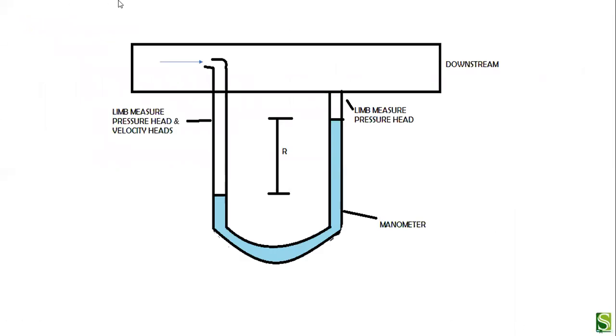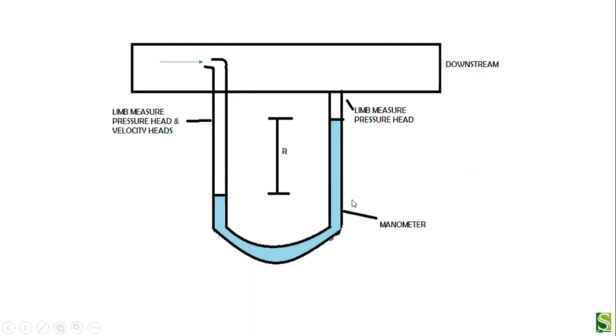This is the diagram of a pitot tube. One tube is in line with the upstream and the other is perpendicular to it. When the fluid flows from the upstream, the velocity increases in the tube and due to that the pressure decreases. The difference in pressure height can be read from the simple manometer connected to the pitot tube. The pitot tube is also known as an insertion meter or insertion tube.